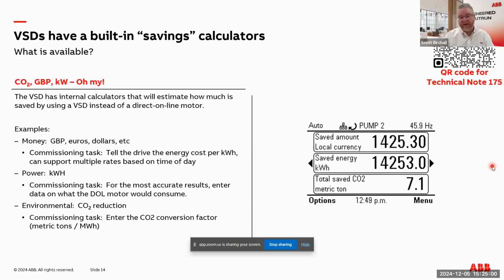So the things you can save or calculate include money, whatever units you want, euros, dollars, whatever. But the drive is only as smart as the commissioning agent - it doesn't know your energy rate. This screenshot was still left at the factory default of 10 cents per kilowatt hour, and nobody's paying that much anymore, which is why the top and bottom lines are off by about a decimal point. But either way, compared to running that motor full speed, this drive has saved over $1,400 in its 6-month lifespan, which is pretty good for only 6 months.